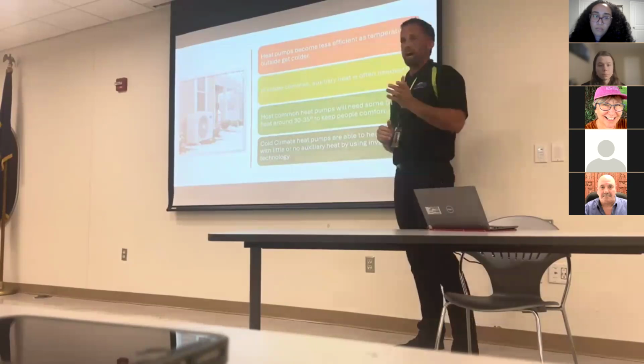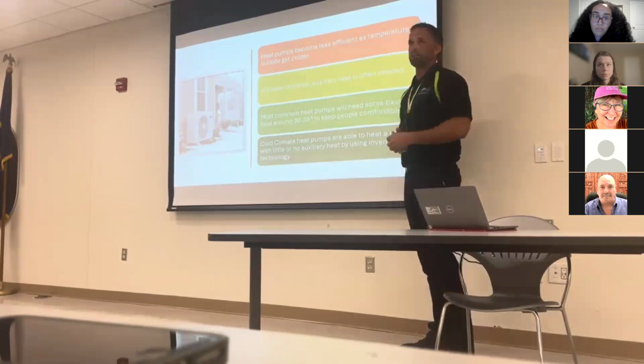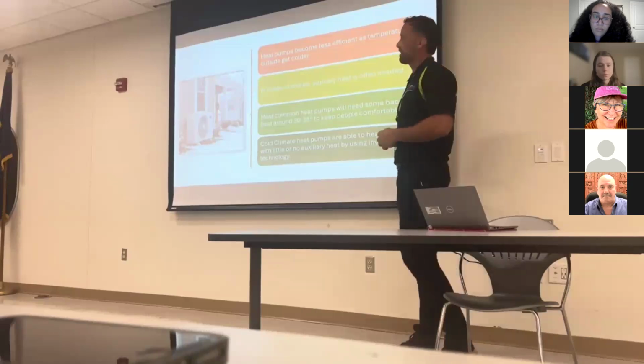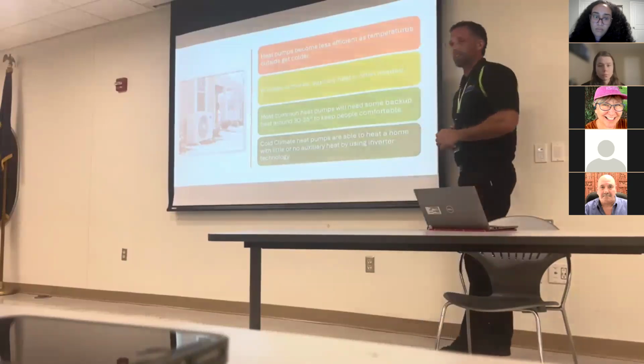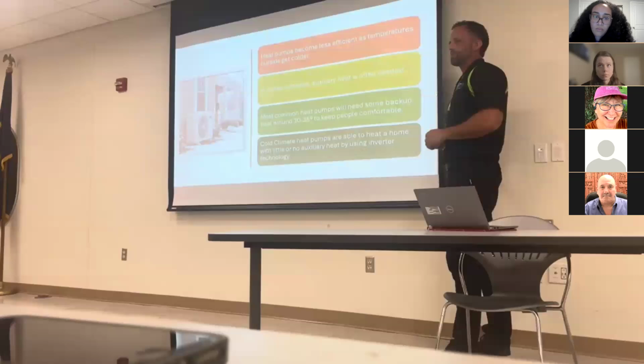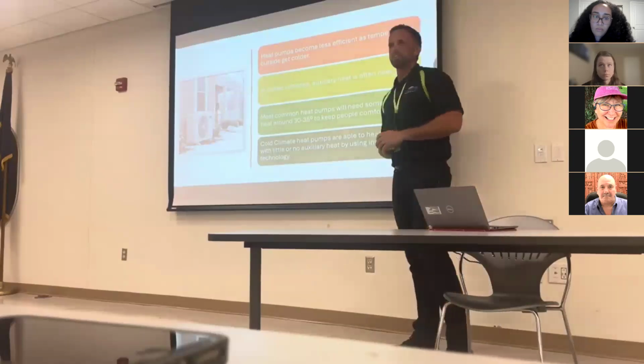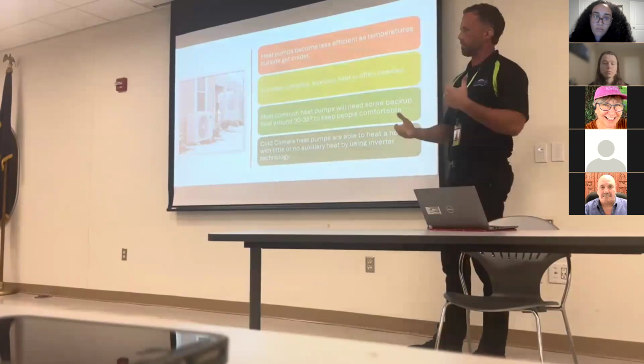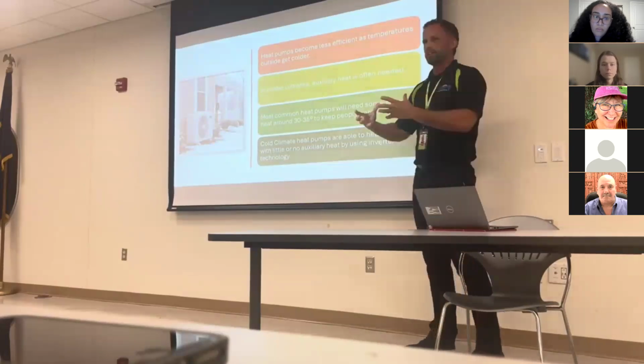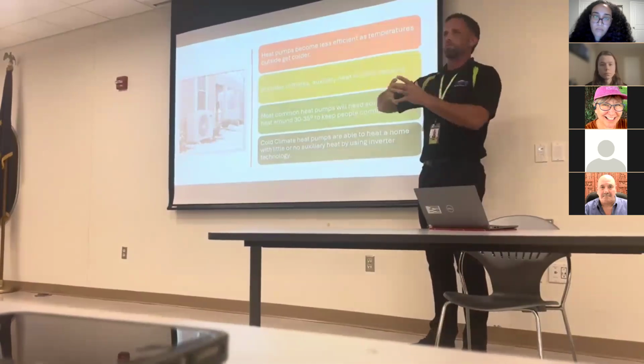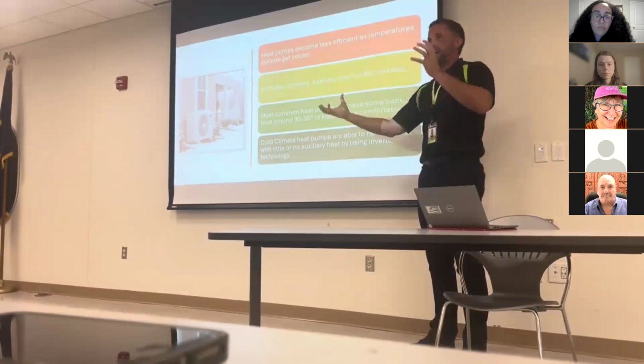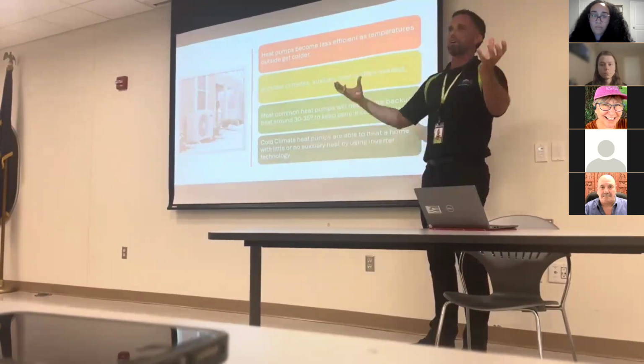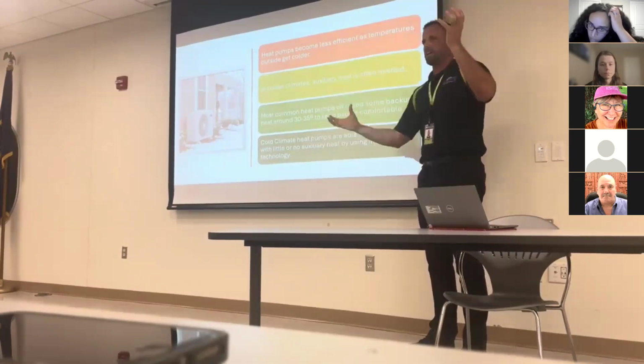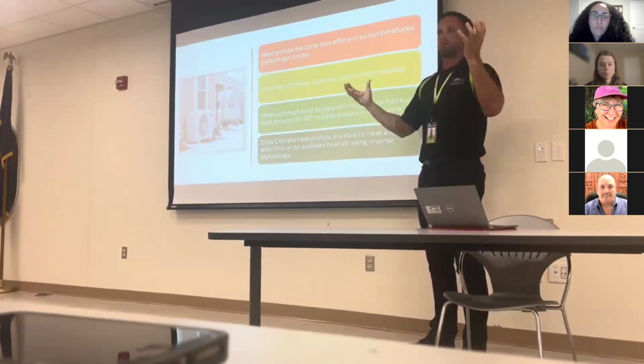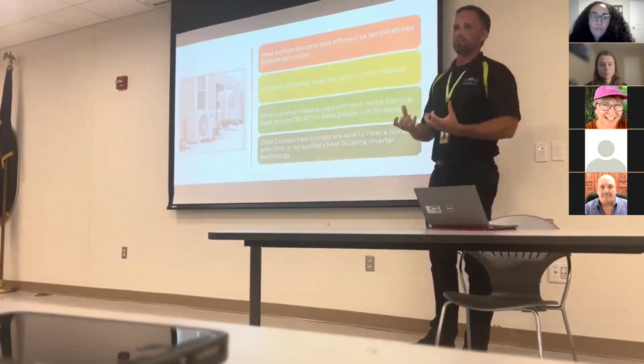That's pretty cool. We do have cold climate heat pumps. We're a Carrier dealer, and Carrier has a couple of lines of cold climate heat pumps. They can work down to -22 degrees and still be pretty efficient. You still need some auxiliary heat with those, usually about 10% of the season. You'll need some type of auxiliary heat with the inverter ones, but they're just much more efficient. Inverter means the compressor is variable, so it ramps up and down. The blower on the inside and the condenser fan motor are also variable. By changing the amount of refrigerant flow and the fan speeds, we can manipulate it a lot more and get more and more heat out of it.